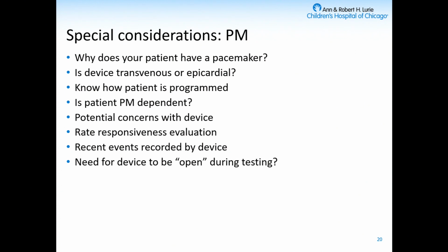It's important to know if it's transvenous or epicardial. Mostly that's important for the person managing the device, but we will often throw the programmer head on the patient. We keep the devices open during testing, meaning we interrogate the device before we start testing, and then we leave that interrogation open. So we can throw the programmer head right on the patient during the test if we want to understand what's happening with their rhythm, or sometimes I'll reprogram the device while the patient's exercising in order to try to improve what I'm seeing in the lab.